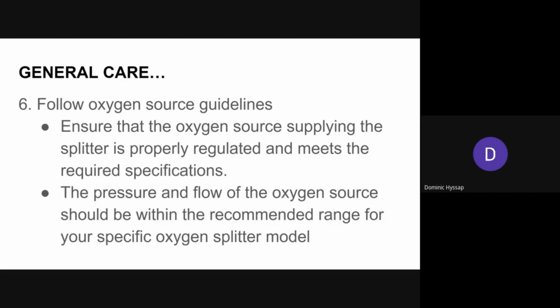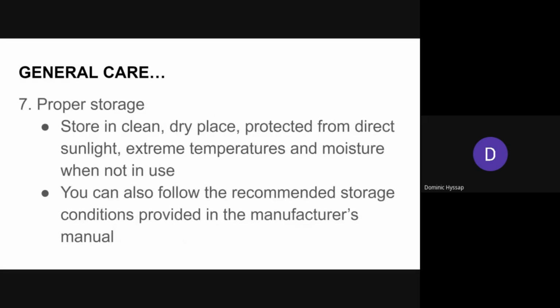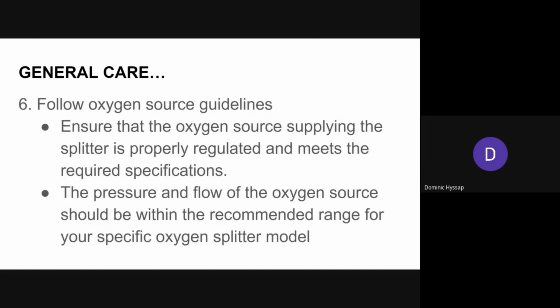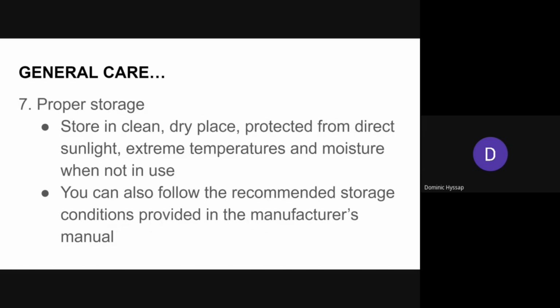It is also important to follow the oxygen source guidelines. That is, we have to ensure that the oxygen source supplying the splitter is properly regulated and meets the required specifications. We also have to ensure that the pressure and flow of the oxygen source are monitored so that it remains within the recommended range for the specific oxygen splitter model. We should also ensure proper storage of oxygen splitters, especially when not in use. These devices should be stored in a clean and dry area that is protected from dust, direct sunlight, extreme temperatures, and moisture. We can also refer to the manufacturer's recommendation for storage conditions if they are provided in the manual.